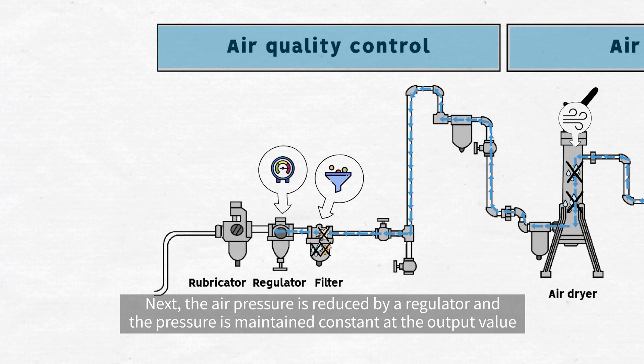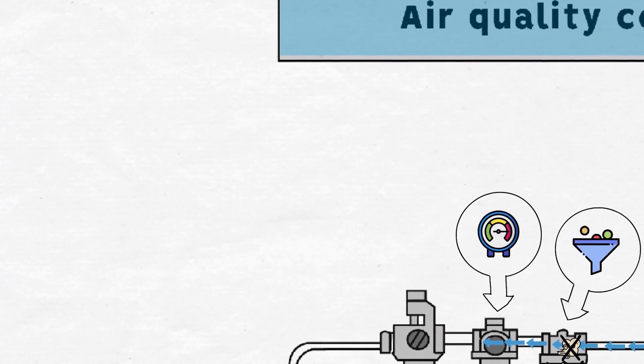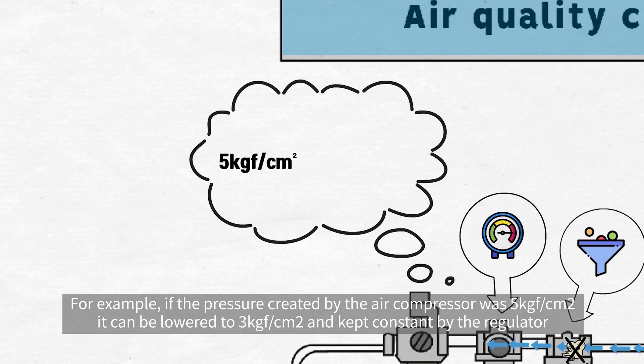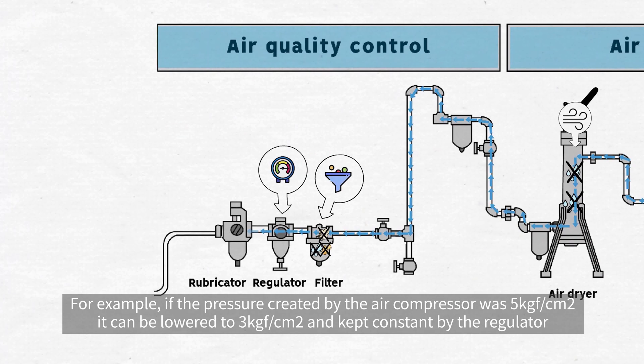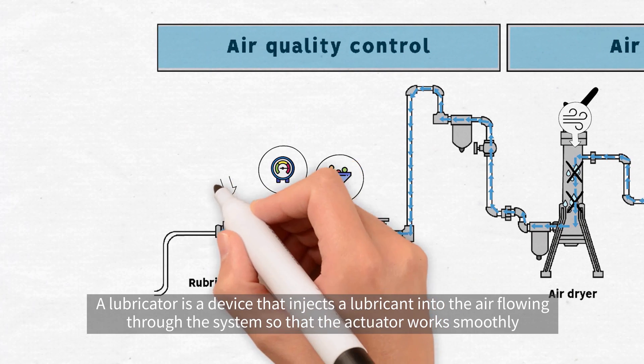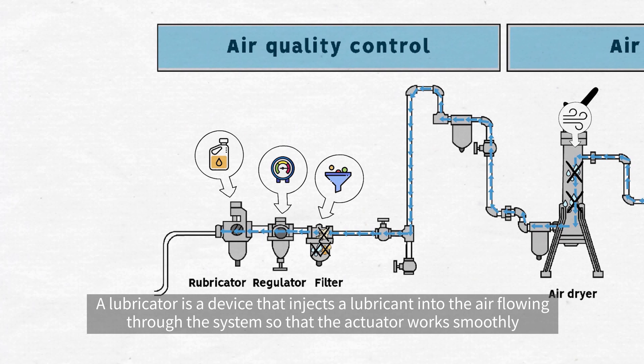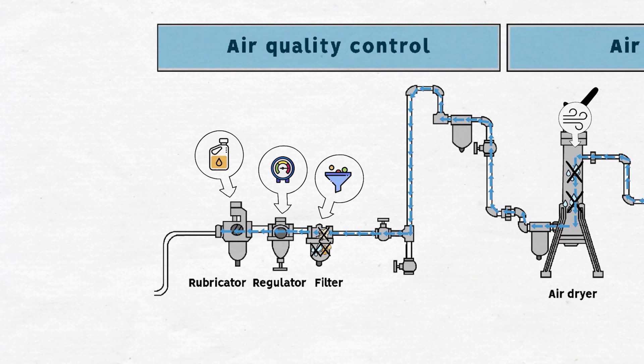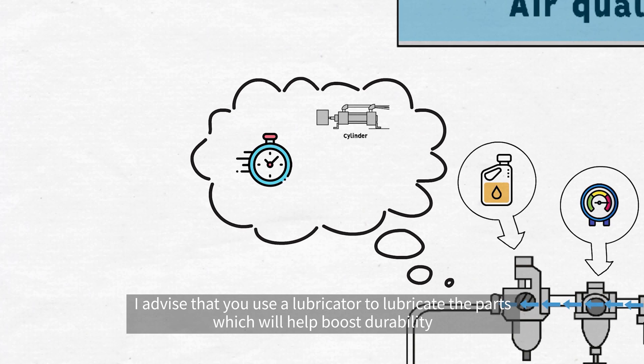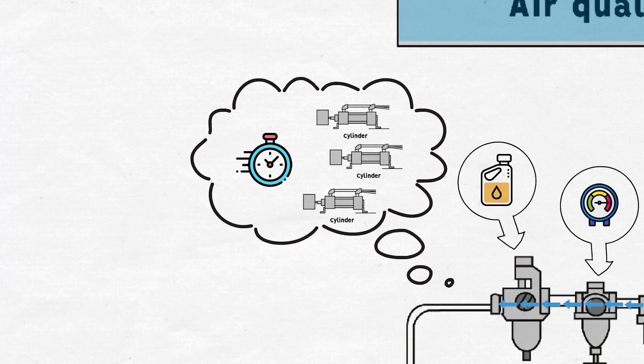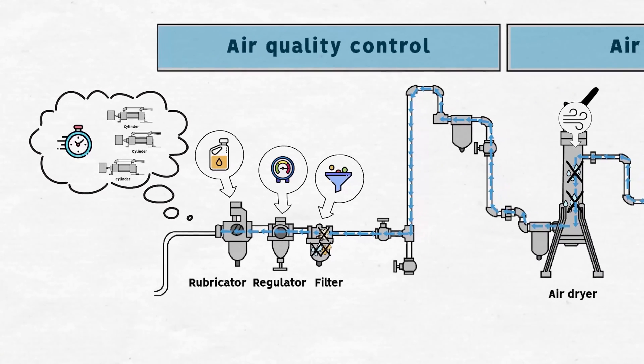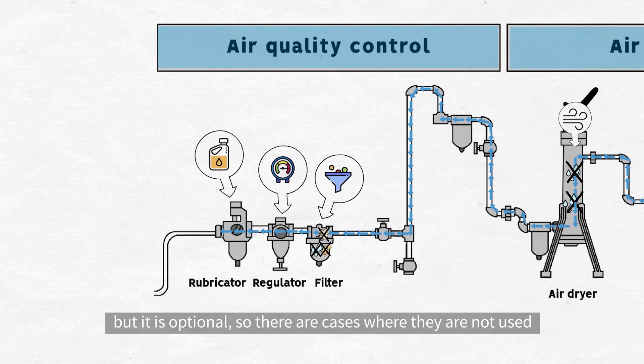Next, the air pressure is reduced by a regulator and the pressure is maintained constant at the output value. For example, if the pressure created by the air compressor was 5 kg of force per centimeter squared, it can be lowered to 3 kg of force per centimeter squared and kept constant by the regulator. A lubricator is a device that injects a lubricant into the air flowing through the system so that the actuator works smoothly. I advise that you use a lubricator to lubricate the parts, which will help boost durability, but it is optional, so there are cases where they are not used.